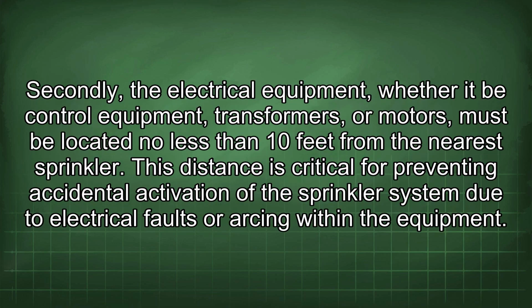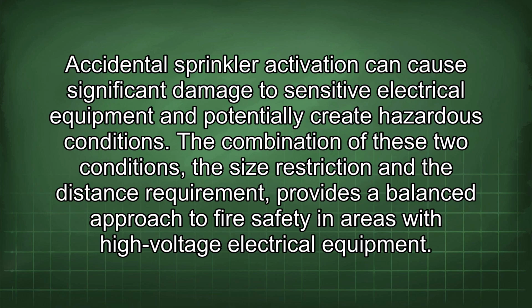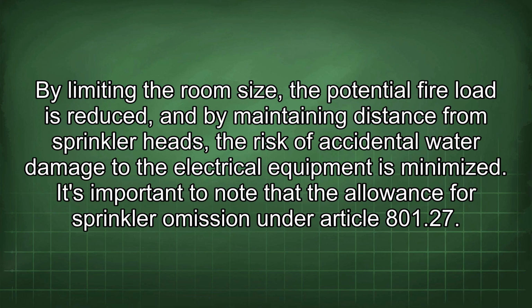Secondly, the electrical equipment, whether it be control equipment, transformers, or motors, must be located no less than 10 feet from the nearest sprinkler. This distance is critical for preventing accidental activation of the sprinkler system due to electrical faults or arcing within the equipment. Accidental sprinkler activation can cause significant damage to sensitive electrical equipment and potentially create hazardous conditions. The combination of these two conditions, the size restriction and the distance requirement, provides a balanced approach to fire safety in areas with high voltage electrical equipment. By limiting the room size, the potential fire load is reduced, and by maintaining distance from sprinkler heads, the risk of accidental water damage to the electrical equipment is minimized.